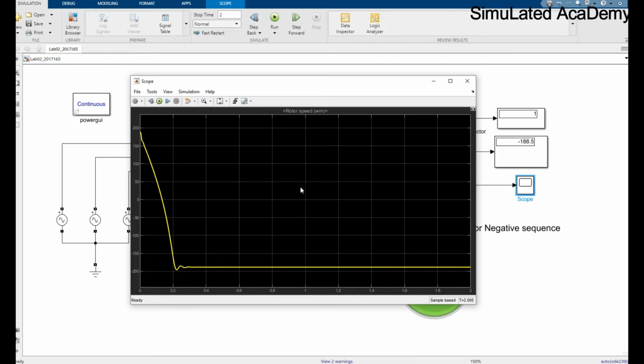In this tutorial, we will determine the phase sequence of a three-phase source. The phase sequence of a three-phase source is the time order in which its three line voltages succeed each other, that is, the order in which they attain their maximum values. A knowledge of phase sequence is important when other three-phase lines are to be connected in parallel, or when the direction of rotation of a large motor must be known in advance.